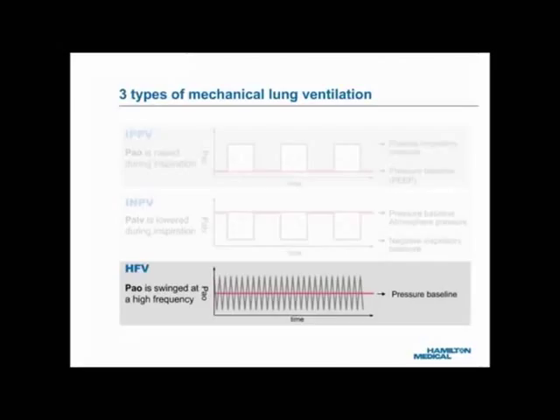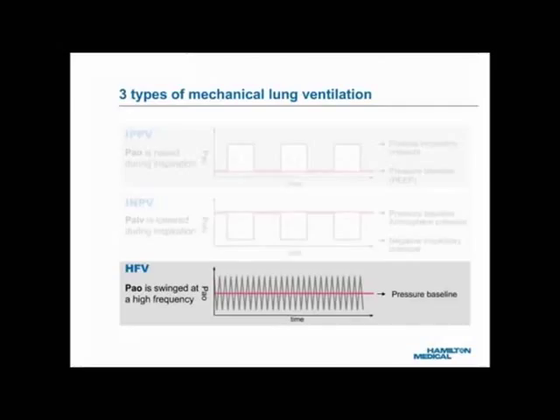Three: the bottom graph shows the pressure waveform of HFV, or high-frequency ventilation. Using this principle, the airway opening pressure, PAO, is swung in a defined range around a defined pressure baseline, at a defined rate, which is at least 150 cycles per minute. Of the three principles, IPPV is the foundation of most modern ventilators, regardless of brand and model. From now on, whenever we say artificial lung ventilation or mechanical ventilation, we are referring to ventilation according to the principle of IPPV.